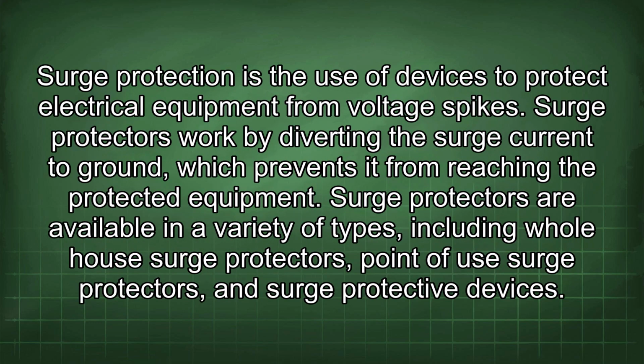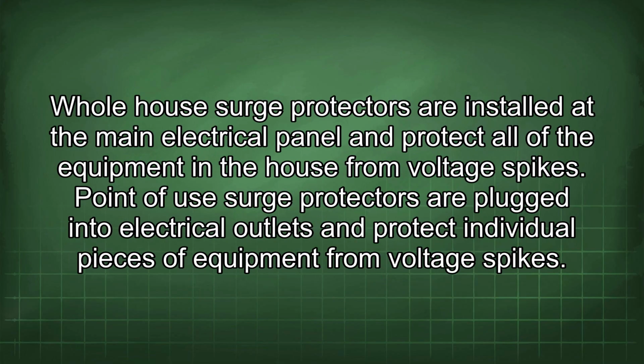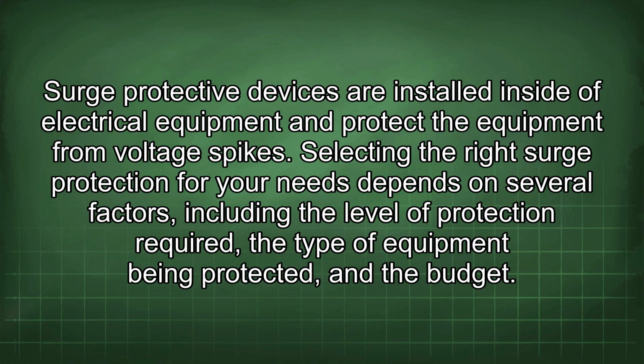Surge protection is the use of devices to protect electrical equipment from voltage spikes. Surge protectors work by diverting the surge current to ground, which prevents it from reaching the protected equipment. Surge protectors are available in a variety of types, including whole-house surge protectors, point-of-use surge protectors, and surge protective devices. Whole-house surge protectors are installed at the main electrical panel and protect all of the equipment in the house from voltage spikes. Point-of-use surge protectors are plugged into electrical outlets and protect individual pieces of equipment from voltage spikes. Surge protective devices are installed inside of electrical equipment and protect the equipment from voltage spikes.